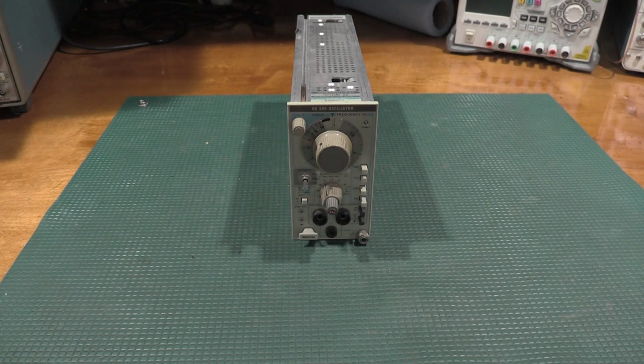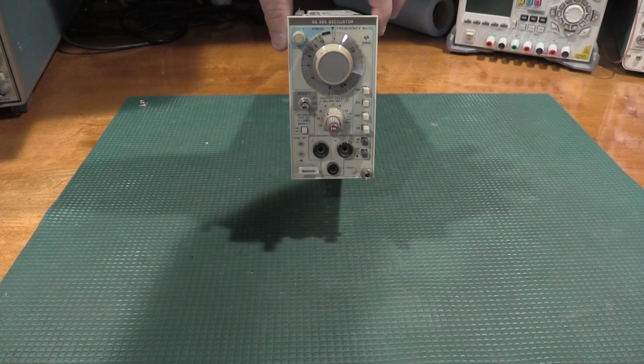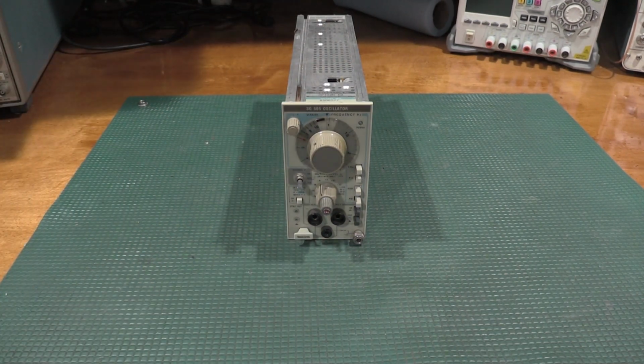I've been very, very hesitant to go into this analyzer because of its distortion specification and what that could possibly mean for repair, because I had no way of validating it. I could validate it to the noise limits of my A501s, which is about 0.0008% THD. Typically on these, they go down to 0.0003. This unit specifically is an option 2, as it has the dual inputs. This is a balanced output, and even the service manual says if you do not have reason to suspect the distortion is off, don't check it, because it is a very lengthy procedure, because this is really getting the signal down into the noise and very hard to work with.